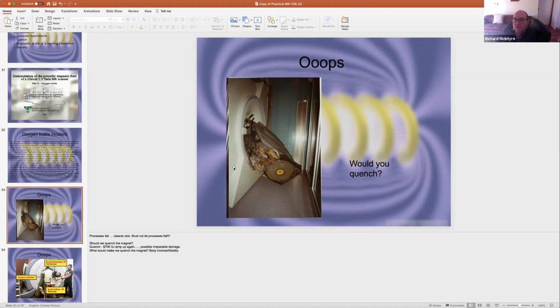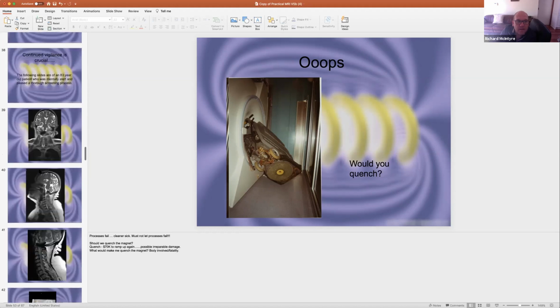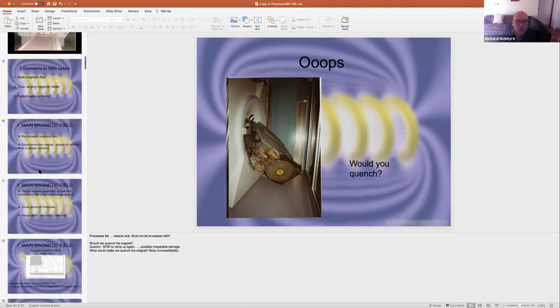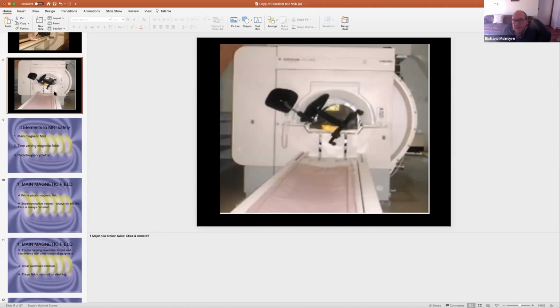So that's why we don't stop that magnetic field when we come to work and we see that the floor buffer's been stuck in the magnet, or that the chair's been stuck in the magnet. We don't quench that machine, because that costs too much money. The engineers come in, they take that current down very, very slowly, which reduces the magnetic field. They take the chair out, and then they re-ramp up the magnet. So they put the current back into the magnet, called ramping.